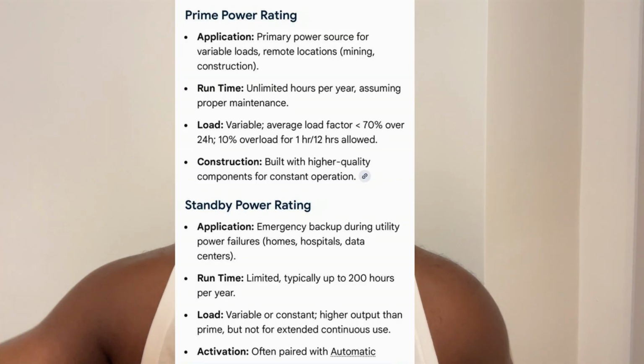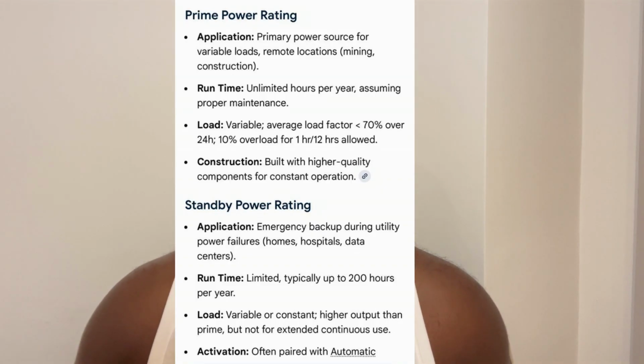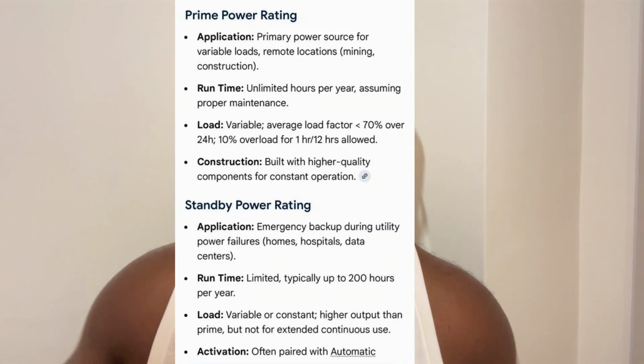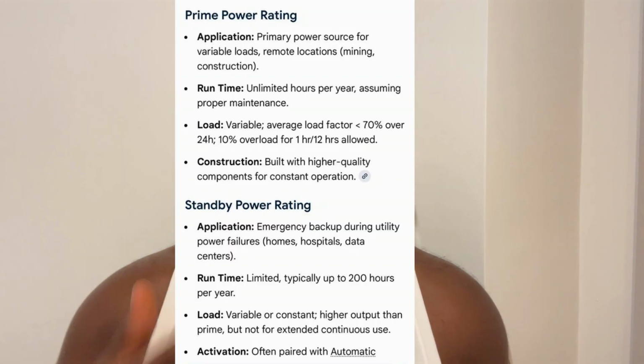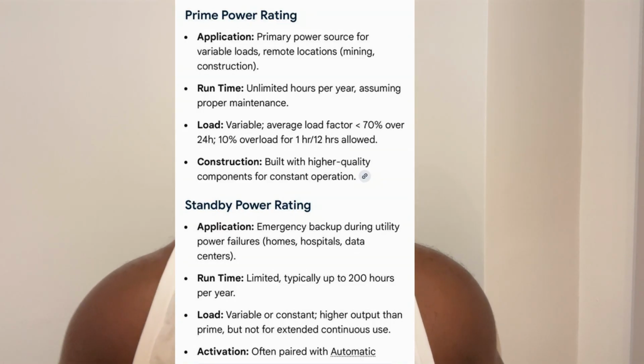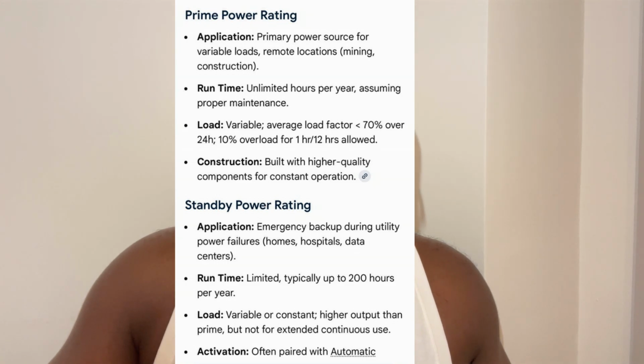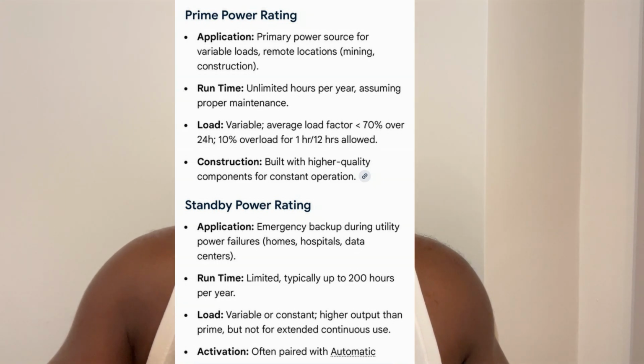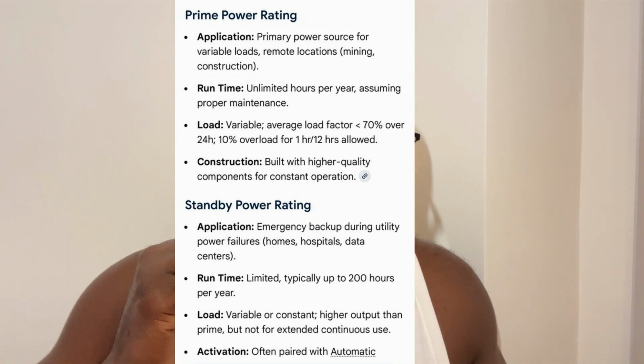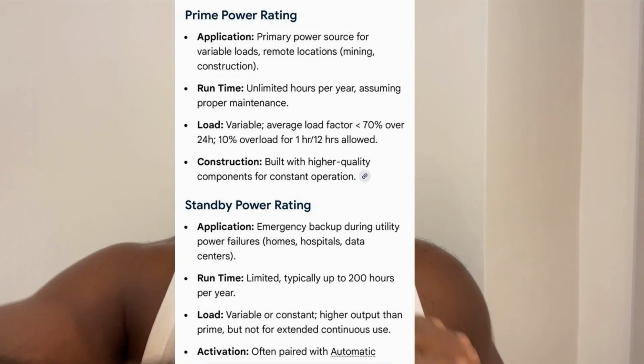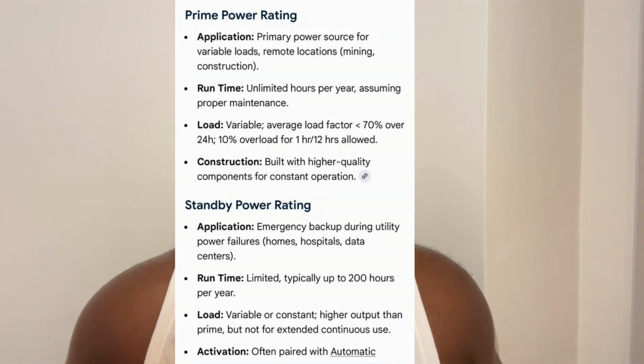It has typically larger fuel tanks, more heavy duty components, and can run 24/7 operation, so therefore typically a bit more expensive. It can also give you a 10% overload for every 1 hour in 12. So what that means is that if you had a generator with prime rating and it says it's 60 kVA, it means it can deliver that 60 kVA of power for an unlimited number of hours in a year, no restrictions.